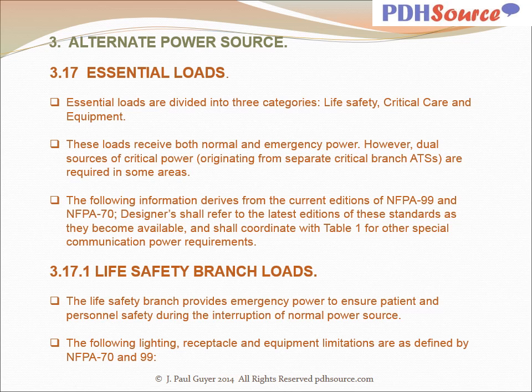Essential loads are divided into three categories: life safety, critical care, and equipment. These loads receive both normal and emergency power. However, dual sources of critical power originating from separate critical branch automatic transfer switches are required in some areas. The following information derives from the current editions of NFPA 99 and 70. Designers shall refer to the latest editions of these standards as they become available and shall coordinate with Table 1 for other special communication power requirements. With regard to the life safety branch loads, the life safety branch provides emergency power to ensure patient and personnel safety during the interruption of the normal power source.